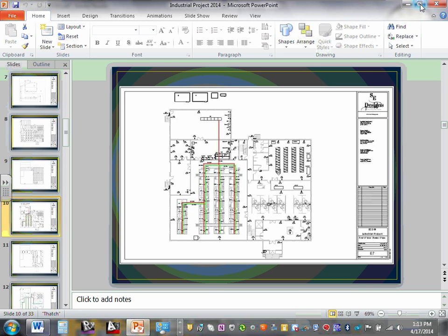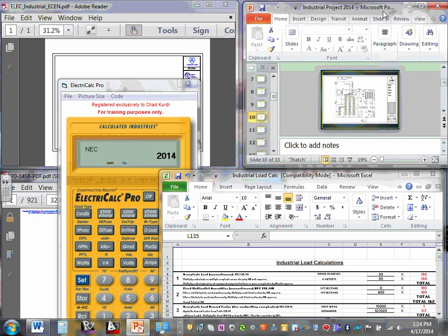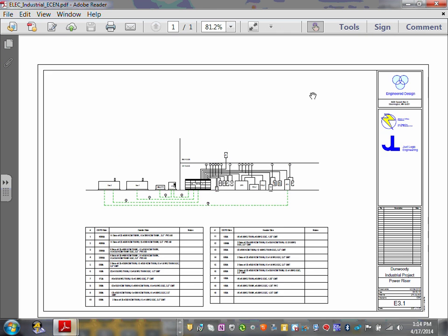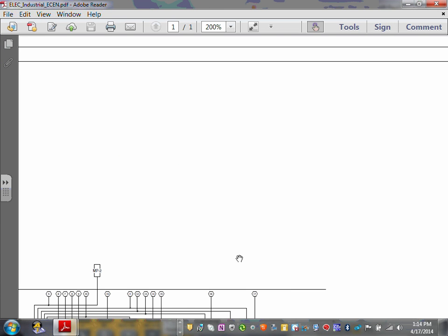Does that make sense? And again, I apologize if it's higher than what some of you electricians are used to, but you can apply this rule to anything. The size of this building is a 4,000 amp switchgear, but the same rules could be applied to a 400 amp panel. Really no difference in terms of the process. So the first thing we need to focus on is the riser, come up with the riser.